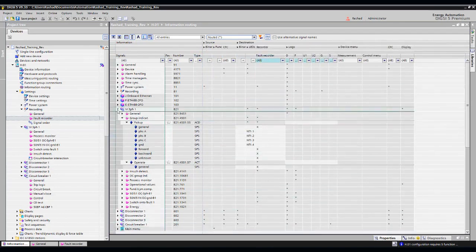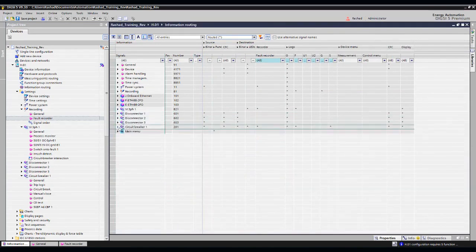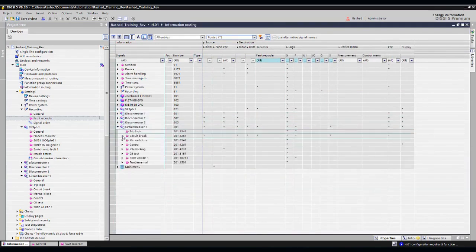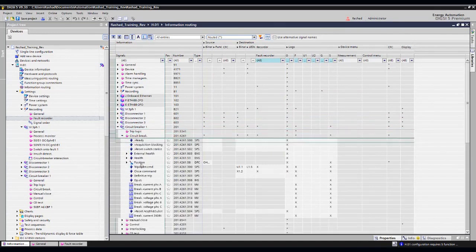Now here, for example, in the circuit breaker, here is the word circuit breaker. And you go here, for example, here is the circuit breaker. Here, it focuses on the word ready to program the input. You tell it active high, it will tell you why is it wrong. You can't just say high or low. It will respond, incorrect format, the format should be H and NN. NN is the column number. I tell it H 1.2 to program input 2 and press enter.